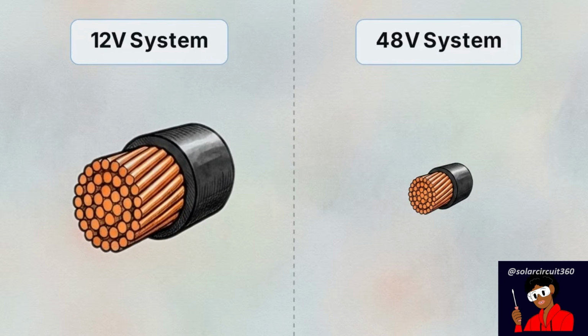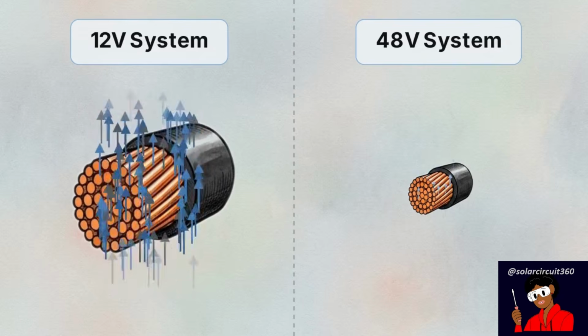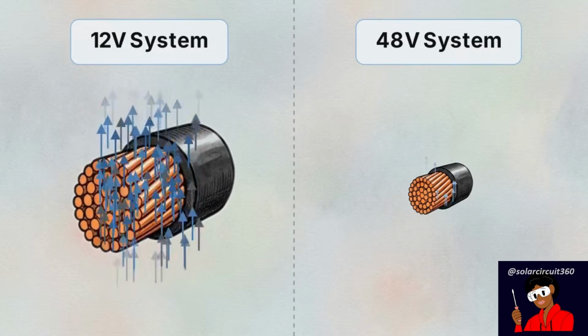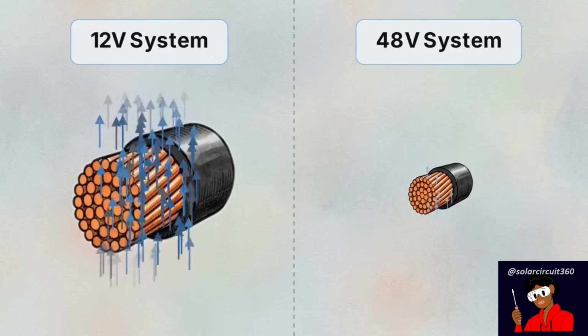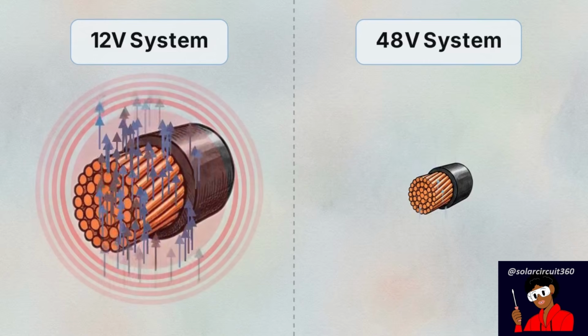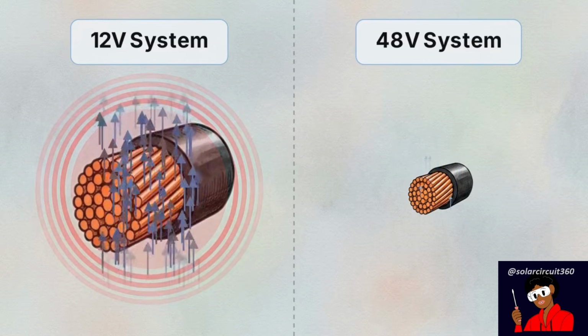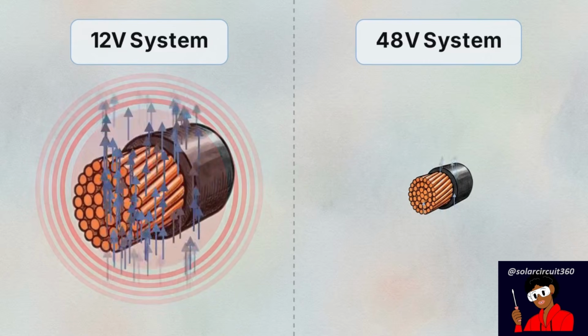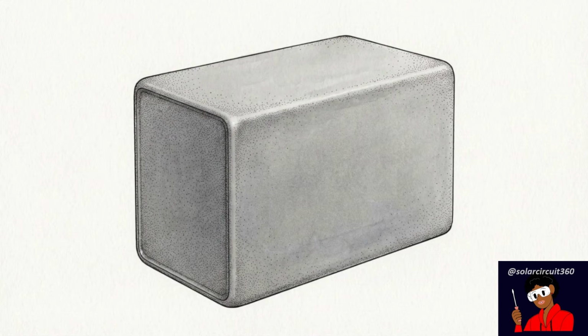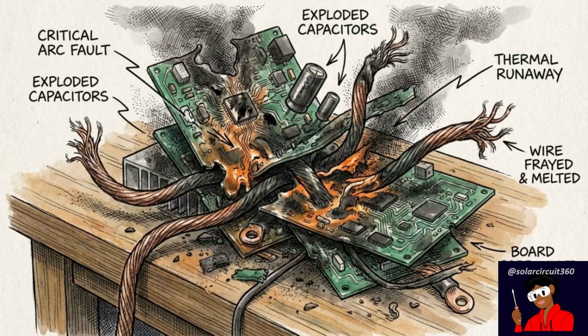This split-screen diagram shows the direct result of voltage scaling. On the left, the 12-volt system struggles with a massive block of current, heating the wire. On the right, quadrupling the voltage to 48 volts inversely drops the current, drastically reducing heat and cable stress. A retail solar generator safely hides this math from you behind a plastic shell, but in a custom build, failing to understand how voltage scales is the leading cause of catastrophic system failure.